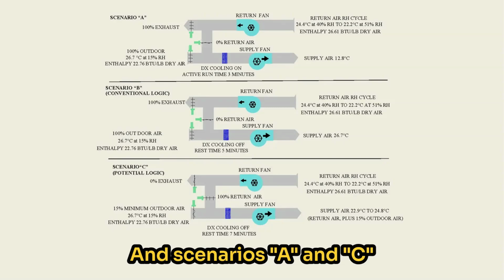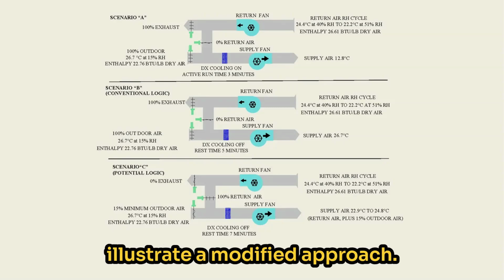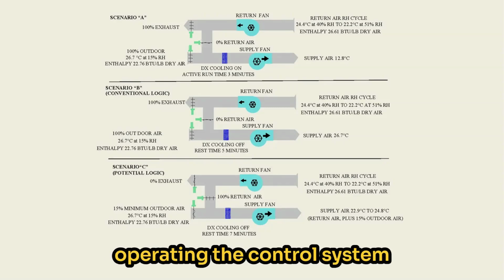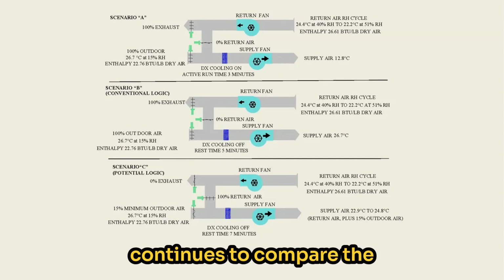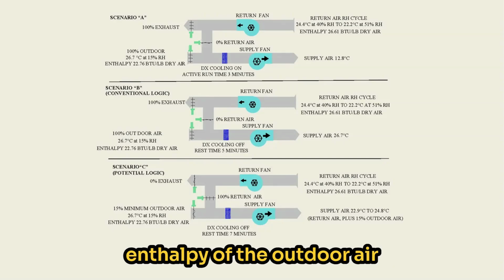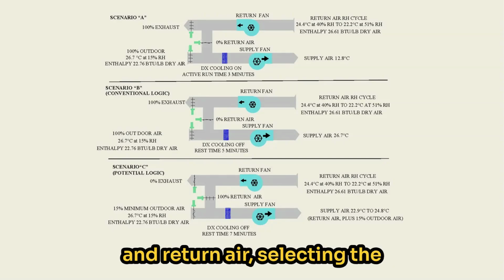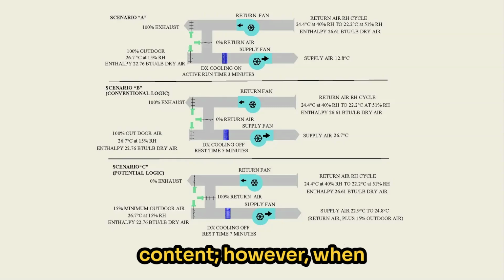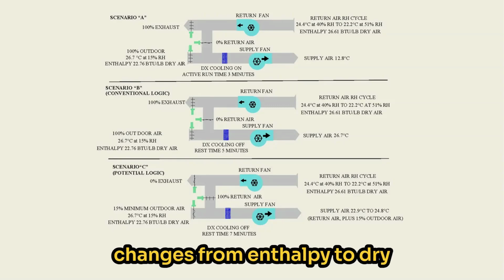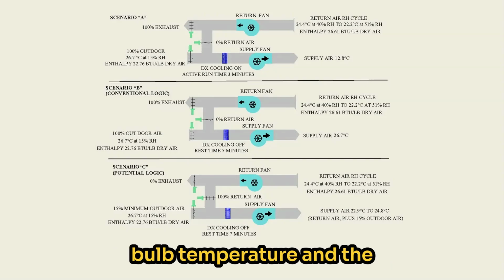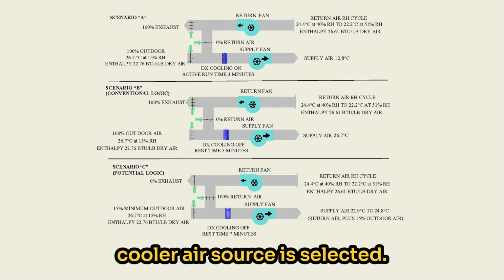And scenarios A and C illustrate a modified approach. While mechanical cooling is operating, the control system continues to compare the enthalpy of the outdoor air and return air, selecting the air source with a lower heat content. However, when mechanical cooling is not operating, the comparison changes from enthalpy to dry bulb temperature and the cooler air source is selected.